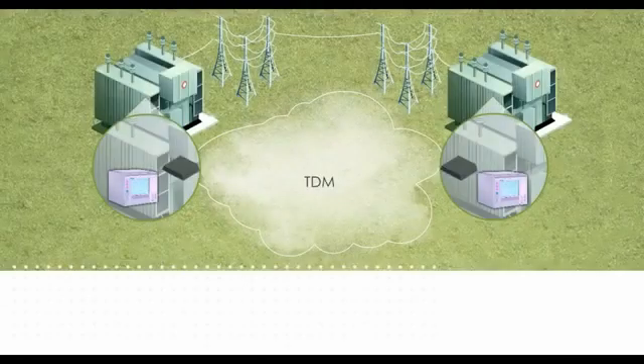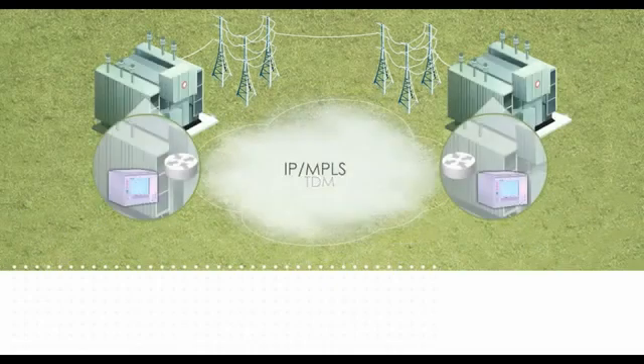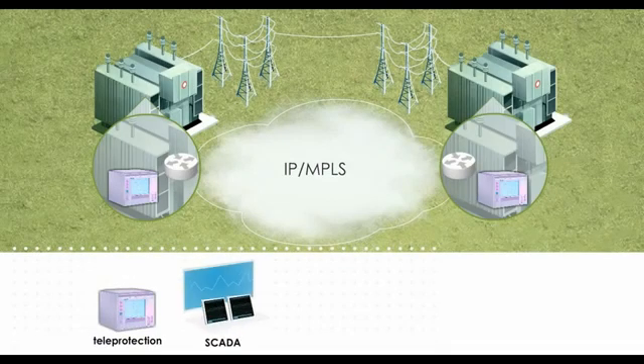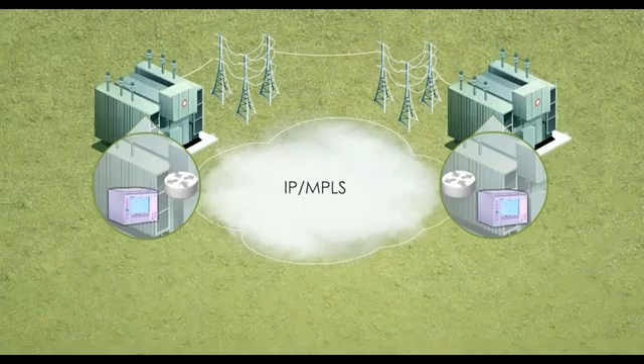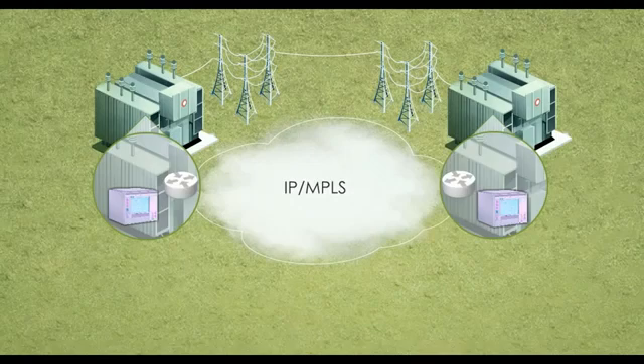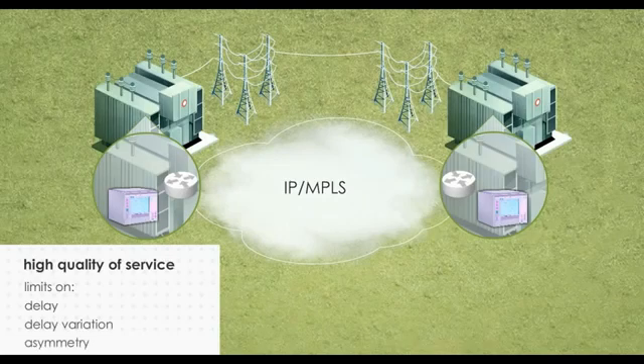With the advent of IP and Ethernet devices in the power systems, many utilities are migrating their communication networks to IP MPLS networks in order to support next generation interfaces and to achieve a converged network infrastructure for existing, new, as well as smart grid applications. From a communication requirement for teleprotection standpoint, it is necessary to continue providing the connectivity between relays with a high quality of service, quantified by limits on delay, delay variation, and asymmetry.